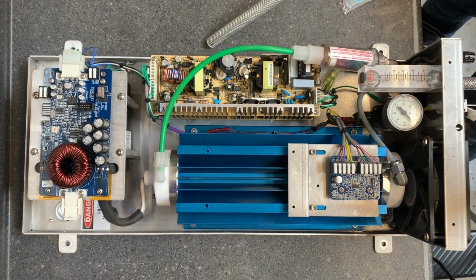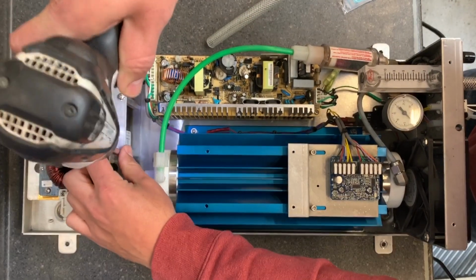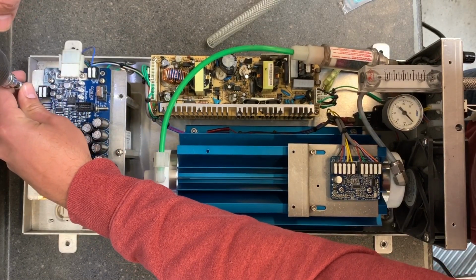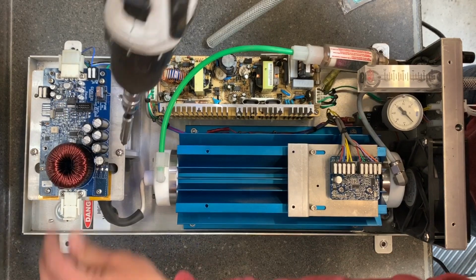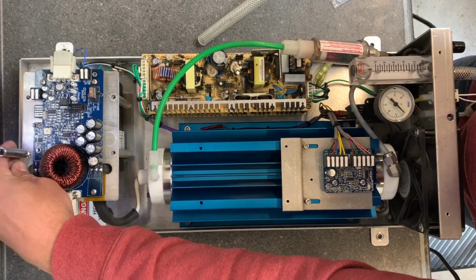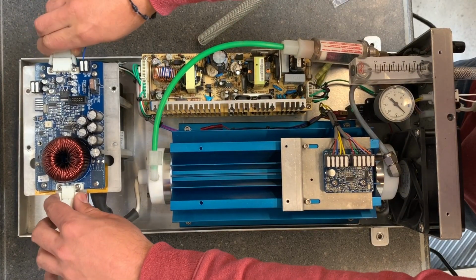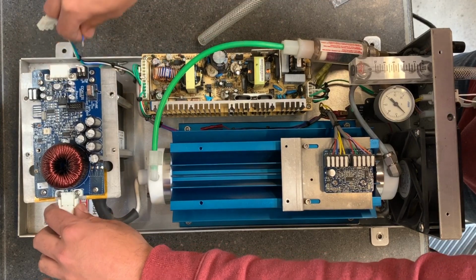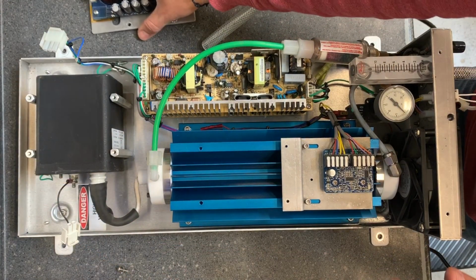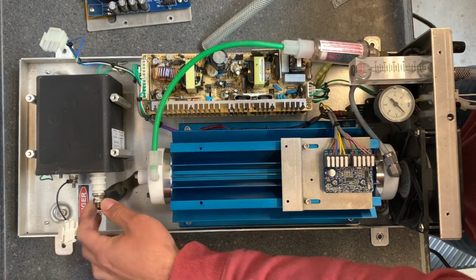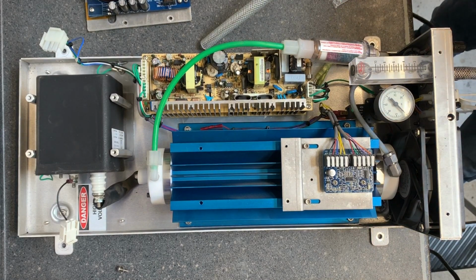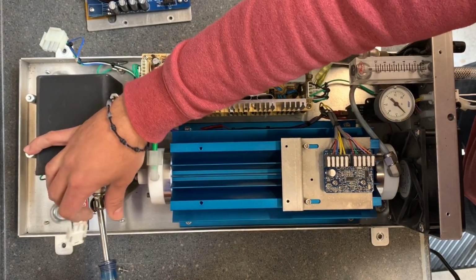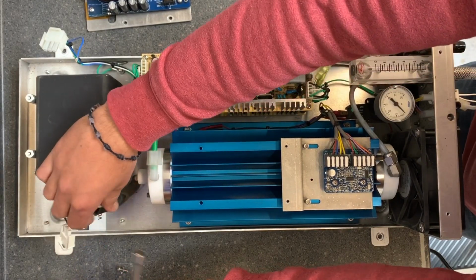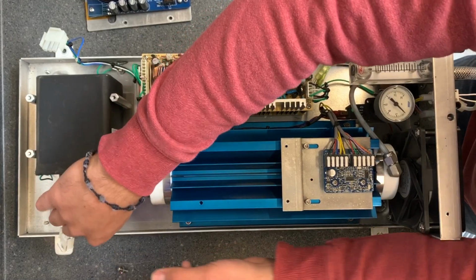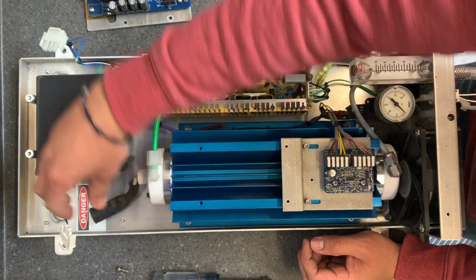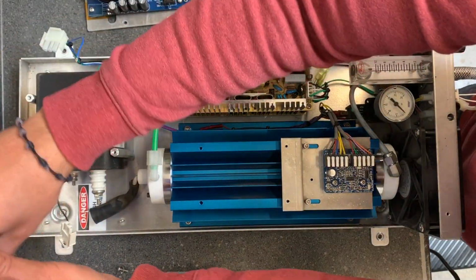First you want to unmount the transformer, which are these 4 screws right here. You want to save your screws. You want to disconnect here. You want to disconnect this blue wire. Disconnect here. Then you can pull the drive board out. You want to disconnect your chamber from the transformer. And you want to do a little shake test to it. You have to unground the transformer before doing so.